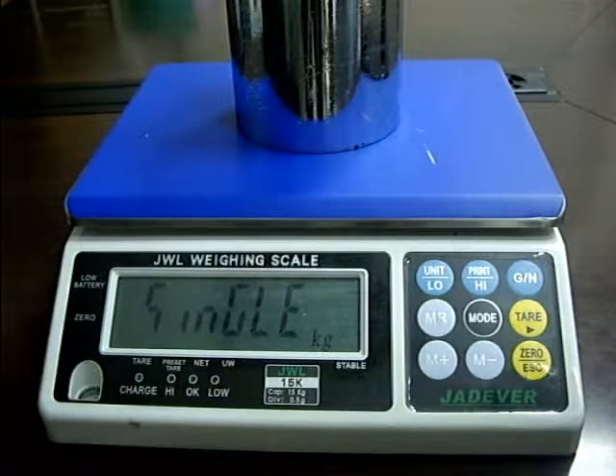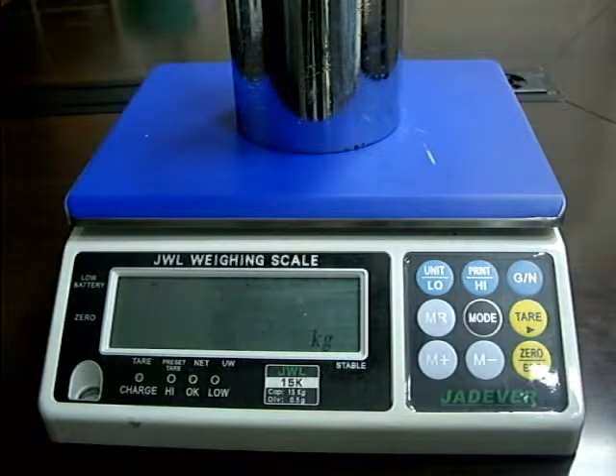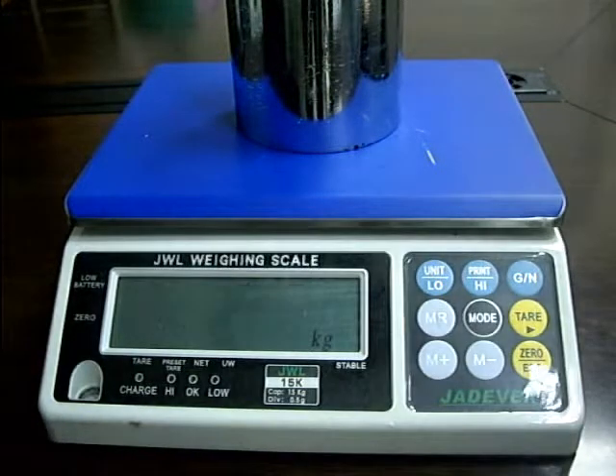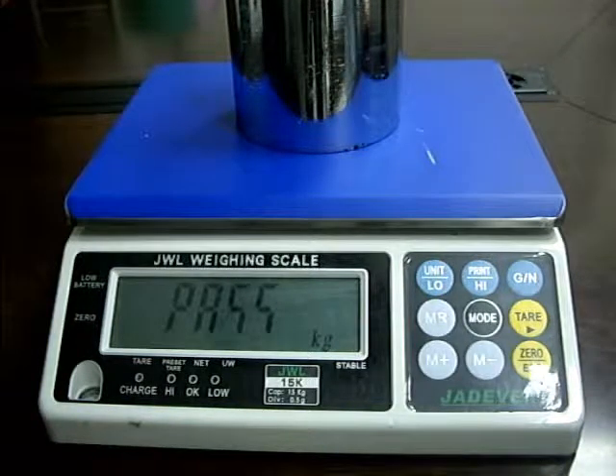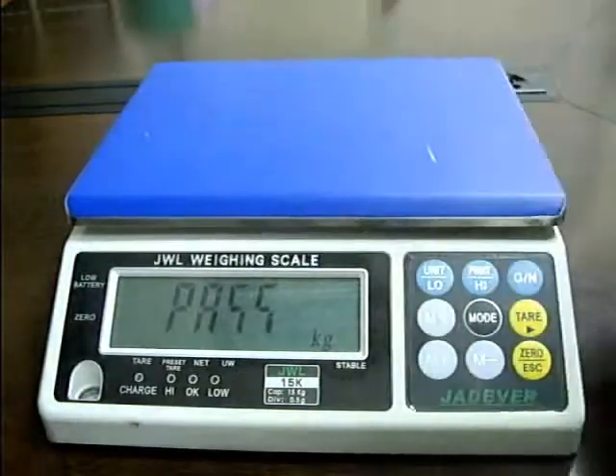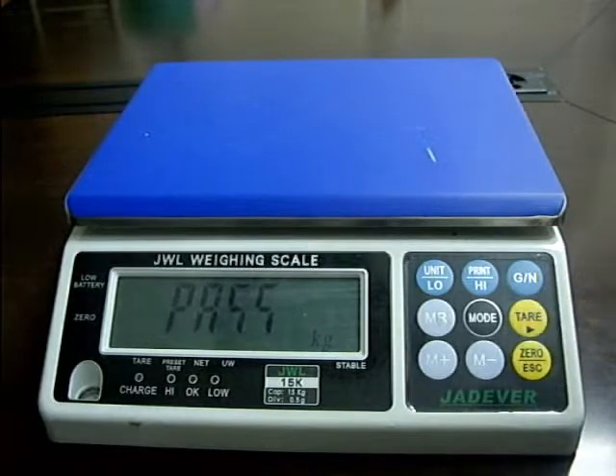The calibration procedure starts. A few seconds later, the calibration procedure is completed with PASS displayed on the screen. Remove all the weights and press key TARE to return to normal weighing mode.